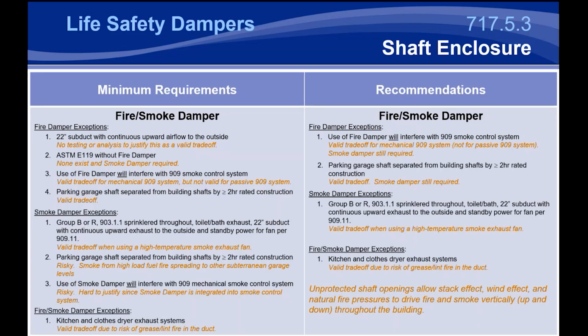Now you do want to use a high temperature fan, so you want to make sure that fan is continuously exhausting. The reason that's a concern is due to what's called reverse stack effect. Now, for a long time, I thought reverse stack effect was one of those theoretical things that could potentially happen. You could have very hot smoke that goes into a cool shaft and actually gets pulled down the shaft if you don't have continuous ventilation. I thought that if that did happen, the smoke would not continue much further down the building to actually cause an issue. It may just stay inside that shaft.